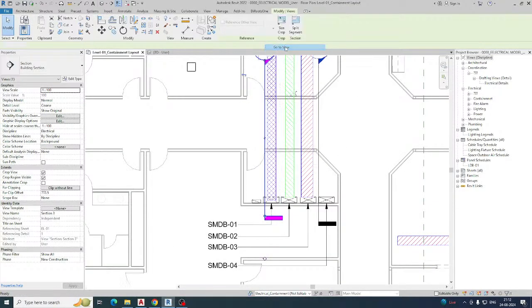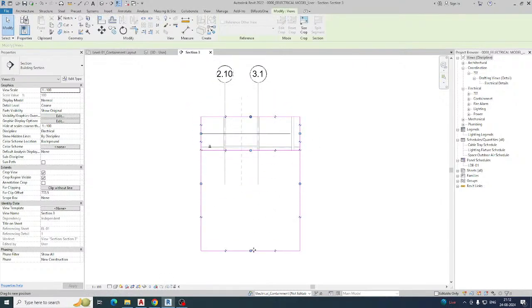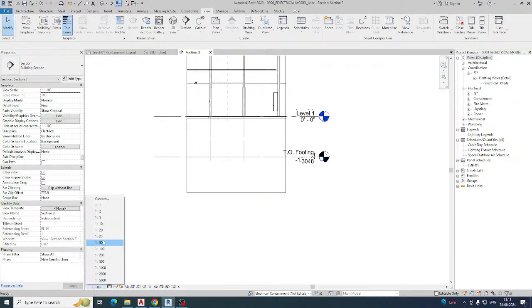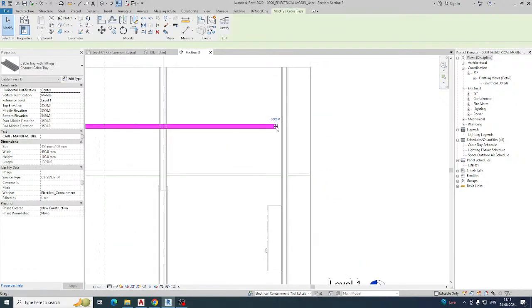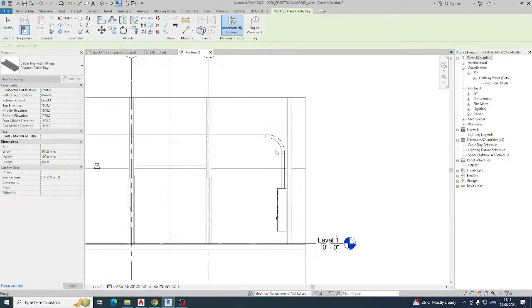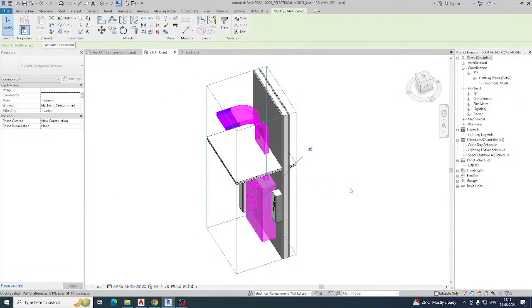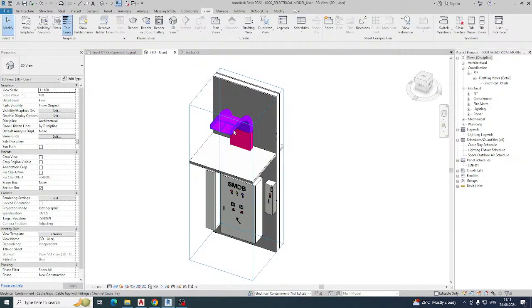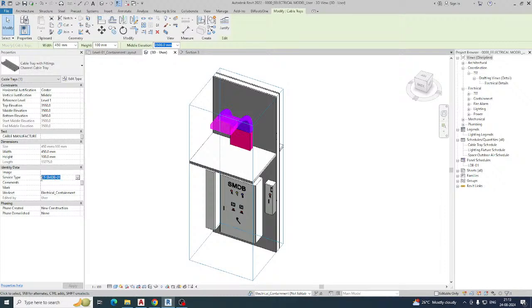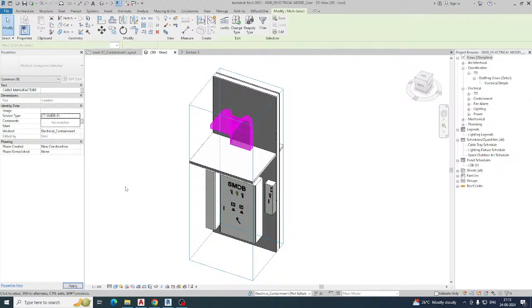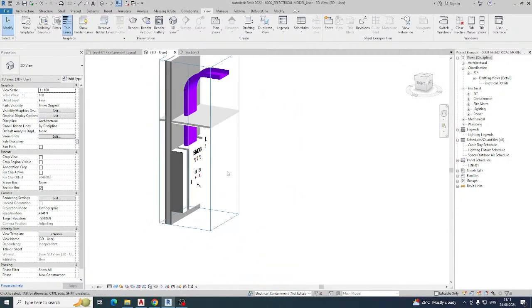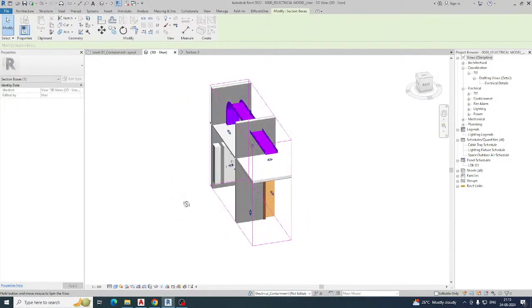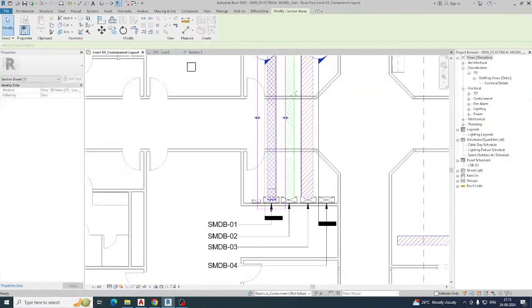Draw a section, stretch it as needed, then click on the section and open the view. Change the drawing scale, then draw the cable tray dropping down to the panel. In the 3D view, you'll see it — if the color looks different, it's because the service type is set incorrectly. Copy the correct service type name — for example, cable tray SMDB 01 — select the element, and assign the same service name for a clear, accurate filter display.